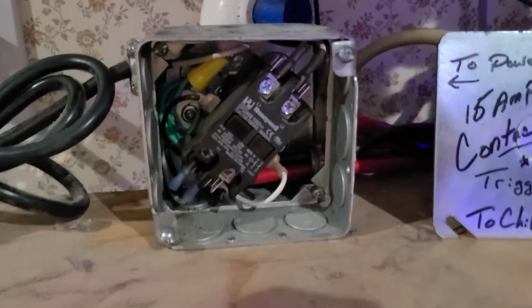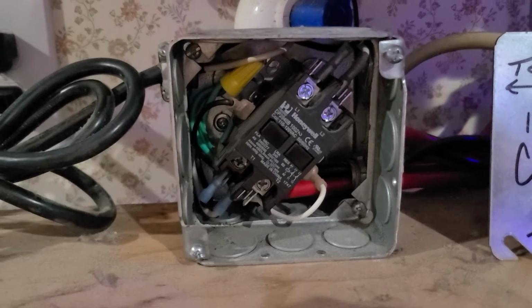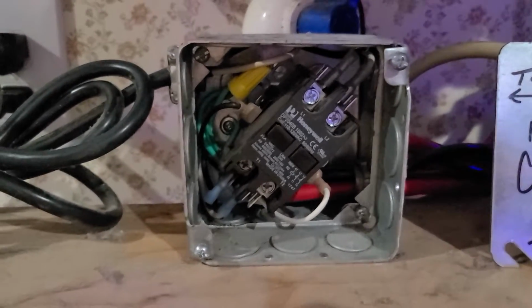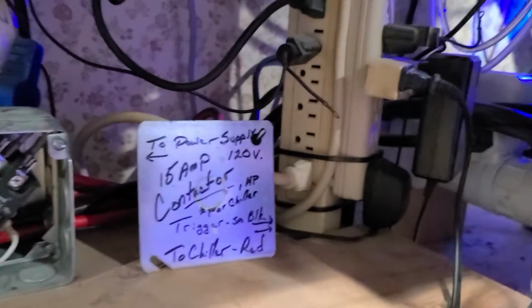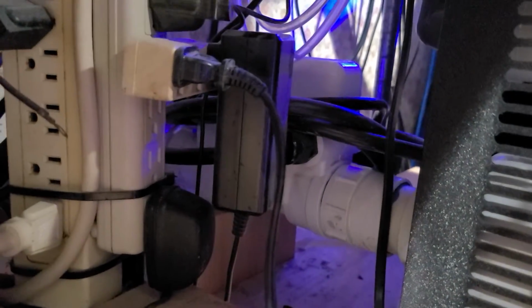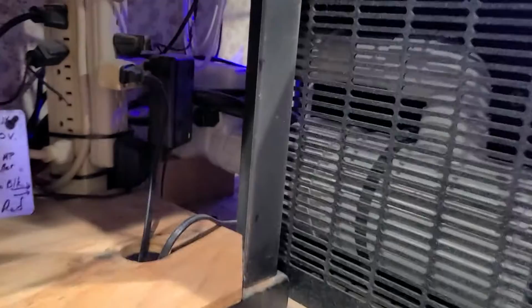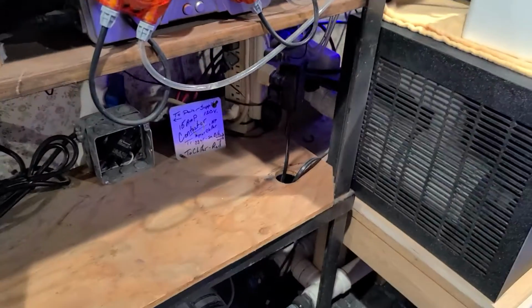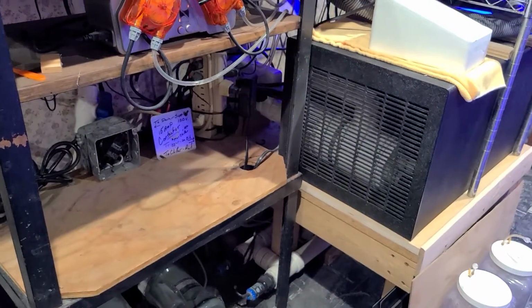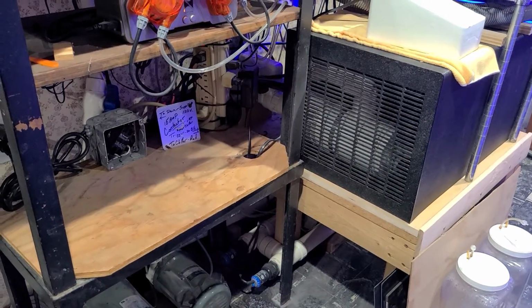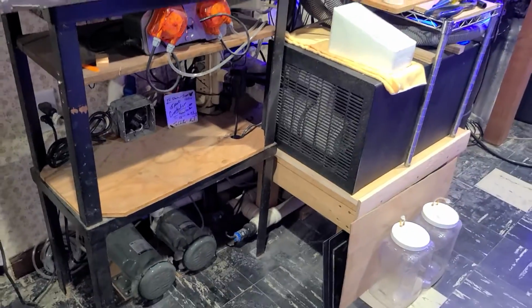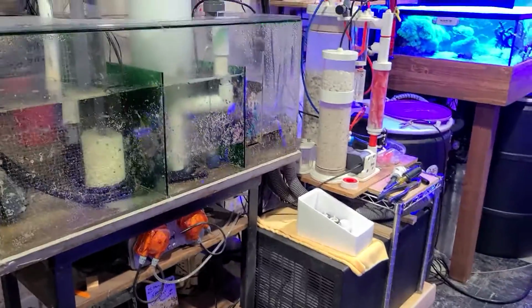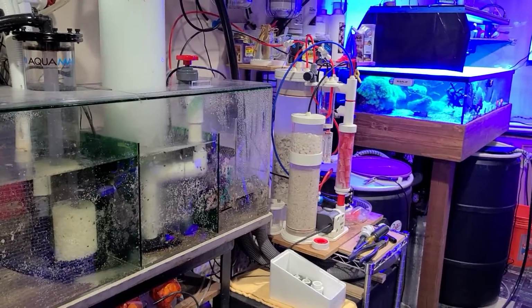So that's my tip of the day as an electrician. Use yourself what they call a contactor on quarter horse and larger chillers. Save yourself a lot of headaches, along with that flow switch back in there. I guarantee it'll be a whole lot less hassle, a whole lot cheaper when it goes haywire. Anyways, my tip of the day from an Ol'skool reefer and an electrician.